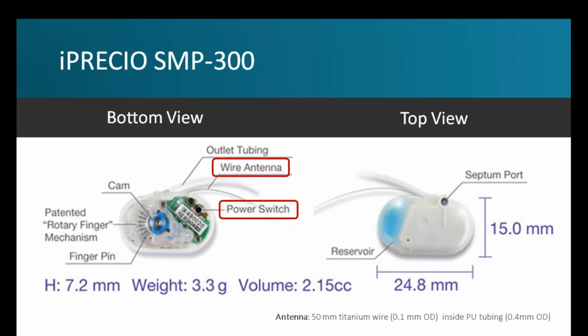And the parts for the SMP 300 pumps are very similar to those of the SMP 200 pump, with some exceptions, obviously. The SMP 300 pumps have an antenna for wireless communication, and they also have a power switch, as shown in the bottom view image on the side. This is an important improvement over the SMP 200 pump that helps conserve battery life before use. The top view image shows the septum port for refilling and filling, and the pump reservoir also, which holds 130 microliters.